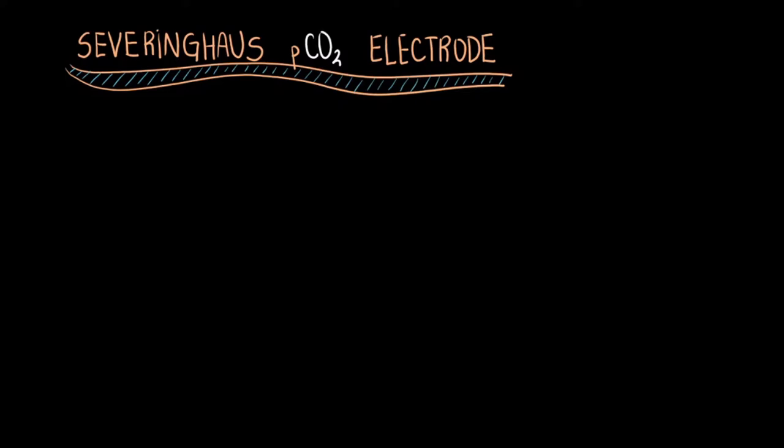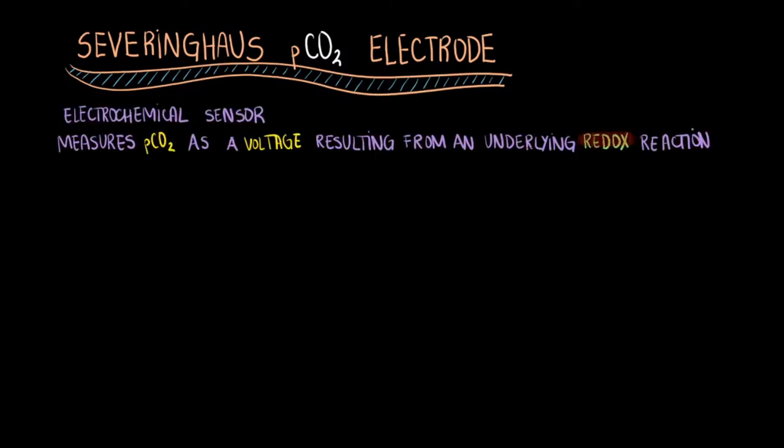The Severinghaus electrode is an electrochemical sensor that measures the partial pressure of carbon dioxide as a voltage using an embedded pH electrode. It measures the partial pressure of CO2 by taking advantage of an underlying redox reaction.